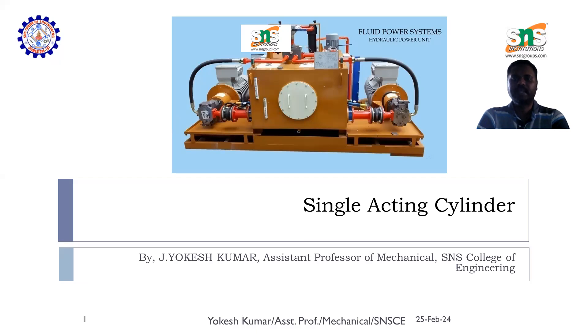Why is it called a single-acting cylinder? Both the single-acting and double-acting cylinders produce linear motion — extension and retraction. But the difference is, in the single-acting cylinder, one motion can be accomplished with the help of fluid power, and the other motion can be accomplished with the help of either gravity or spring force. That's why it is called a single-acting cylinder. Most commonly, extension is accomplished with fluid power and retraction with gravity or spring force, though this can change depending on the application.